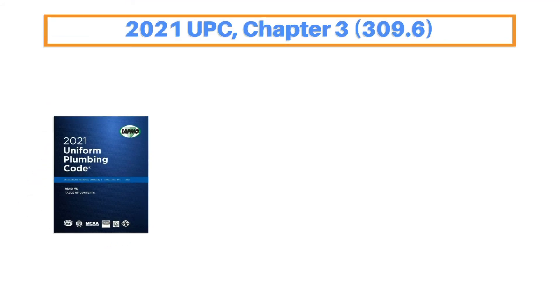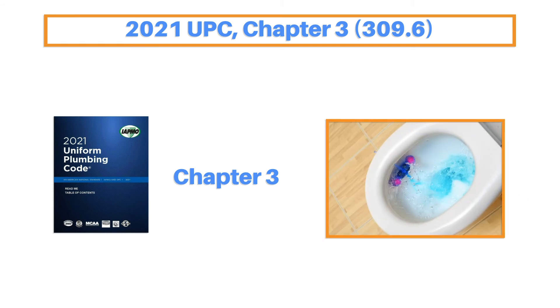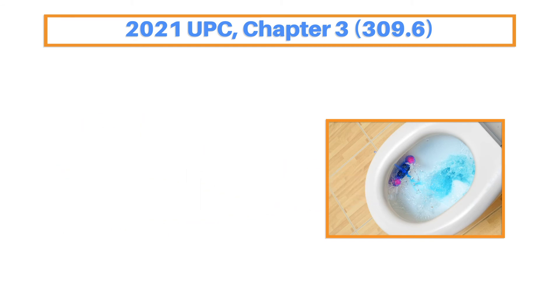The new requirement for these situations is found in Chapter 3 of the 2021 UPC. While it's impossible to prevent dead legs in a plumbing system, the new requirement mandates that dead legs have a method of flushing, in order to protect the public from any dangers from the stagnant water.